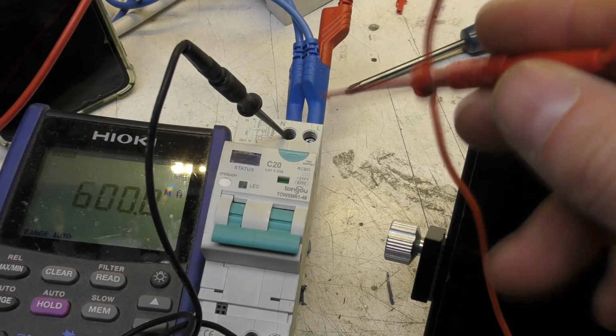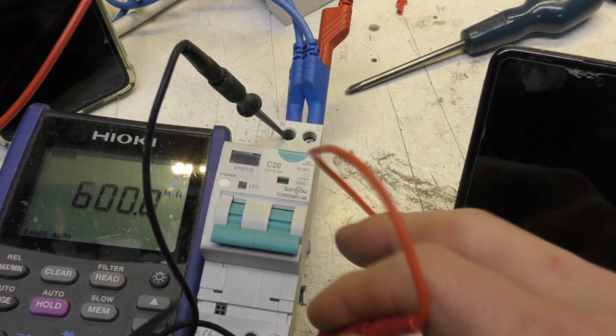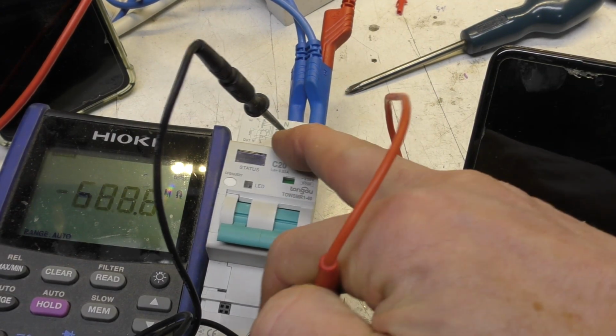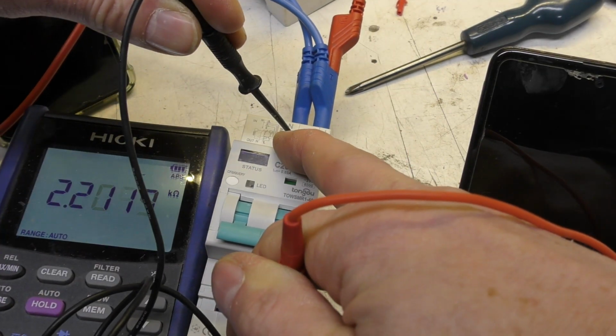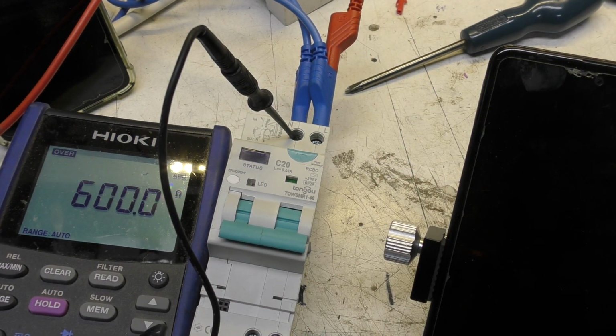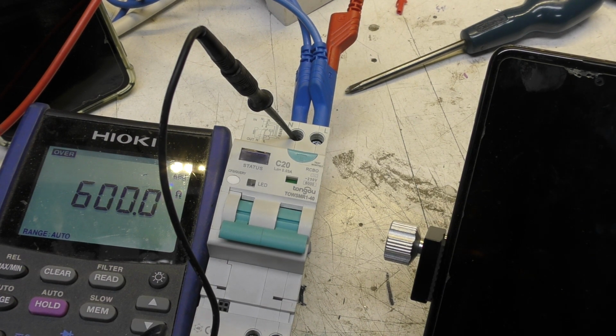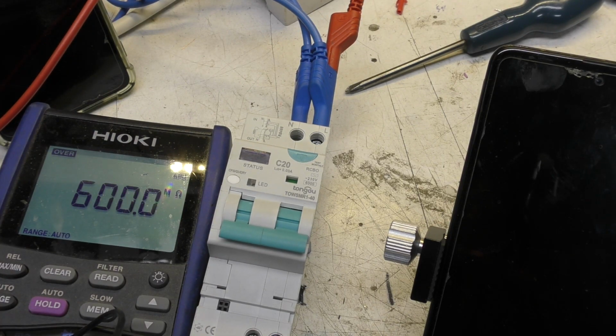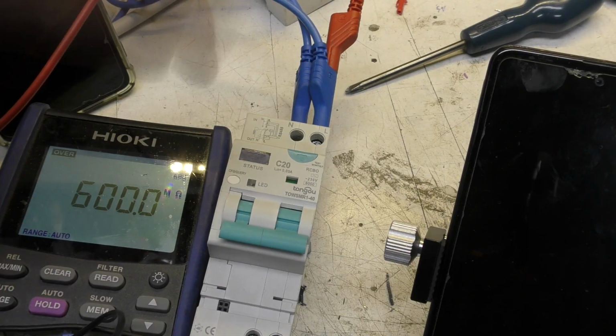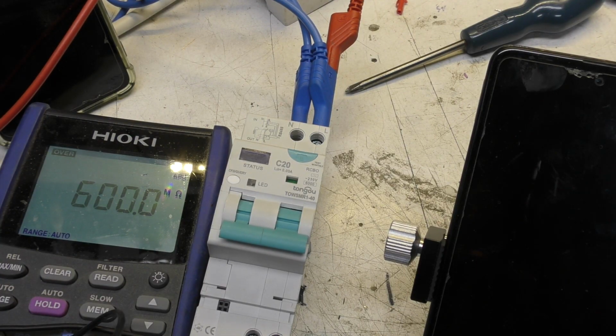Actually, I've just turned it off and I was going to measure the resistance between neutral in and live out. When I press that button, we can see we've got about 2.2k across there for that resistor, which at 240 volts will dissipate about 26 watts. So I suspect that resistor won't last very long if you disable the RCD function and keep pressing that button. And again, in a scenario where someone's not familiar with this thing, they might find, okay, the thing's not tripping, press the button, why is it not tripping? And suddenly the thing's probably going to burst into flames.